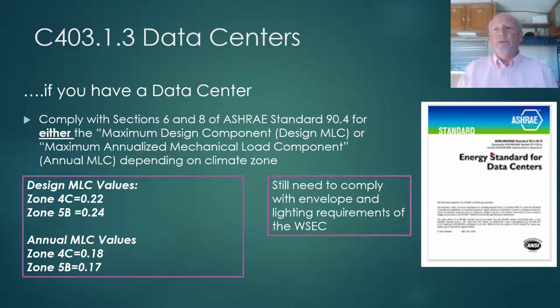So, design MLC values is the ratio of the design HVAC load divided by the design ITE equipment load. For example, the design HVAC load would include the cooling compressors, pumps, heat rejection equipment, and air handling fans at design conditions. So the total kW of that load divided by the total design IT load at 100% load. In other words, when you have a design MLC value of 0.22 for zone 4C, that means that the HVAC load cannot exceed 22% of the design ITE load, or in climate zone 5B, 24%.